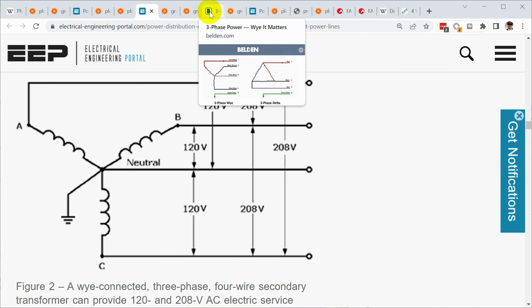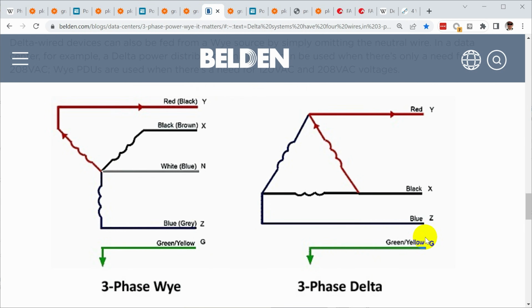So that brings us to the other kind of configuration that we commonly see, and that's called three-phase delta. The difference between three-phase Y and three-phase delta is that the delta has no neutral. You simply have your three phases. They're labeled XYZ here. They're sometimes called XYZ, sometimes called ABC, sometimes called L1, L2, L3. But you only have those three legs, and if you measure the voltage between any two legs, you will see 240 volts. So that's actually higher than the 208 volts.